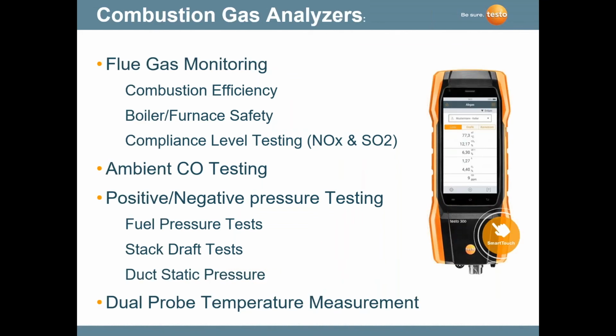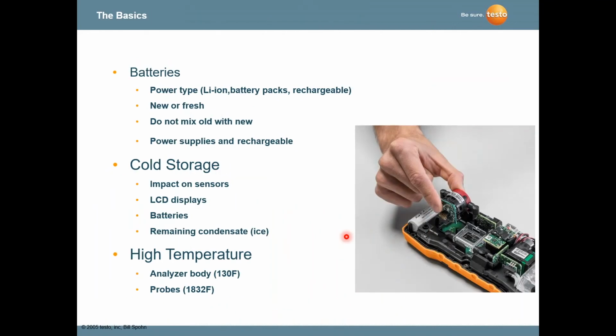Flue gas combustion analyzers are good for combustion efficiency, safety, and compliance, as we talked about. Ambient CO testing: it does have pressure sensors in. Not all instruments have pressure sensors. Testo's does, but you can use positive pressure, negative pressure, and dual pressure in our instruments. And you can have not only one temperature probe in the stack, but also another temperature probe in the primary air.